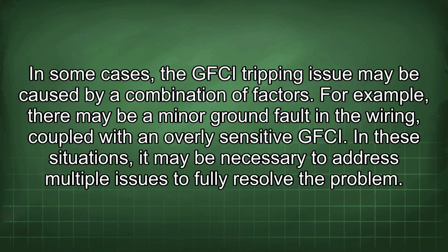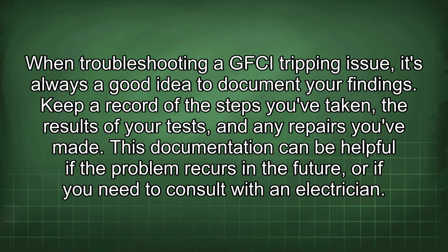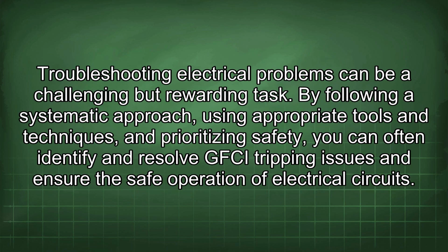In some cases, the GFCI tripping issue may be caused by a combination of factors. For example, there may be a minor ground fault in the wiring, coupled with an overly sensitive GFCI. In these situations, it may be necessary to address multiple issues to fully resolve the problem. When troubleshooting a GFCI tripping issue, it's always a good idea to document your findings. Keep a record of the steps you've taken, the results of your tests, and any repairs you've made. This documentation can be helpful if the problem occurs in the future, or if you need to consult with an electrician. Troubleshooting electrical problems can be a challenging but rewarding task.